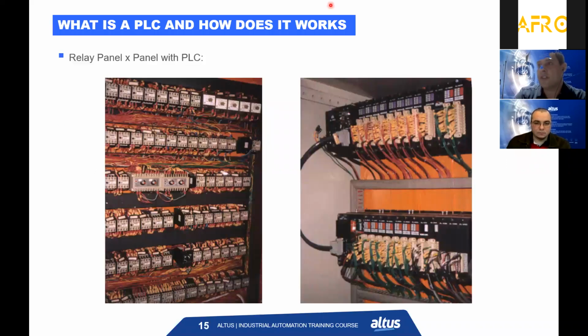Here you can see the picture of a relay panel from the 70s or 80s, and how clean it is using an old model of our PLC. This is an AFRO-ALTUS PLC, an older one, maybe from the 80s. And you will see that your cabinet is much cleaner compared to this. So we do all the logic inside here and substitute every interlock logic that we have here.